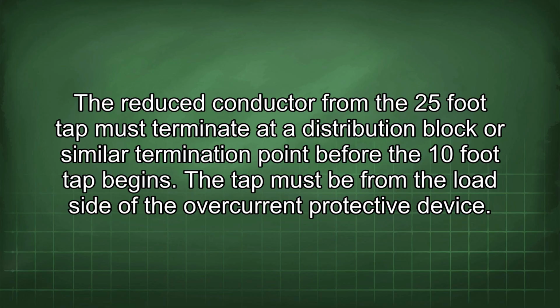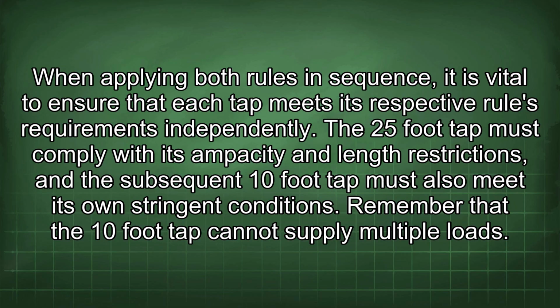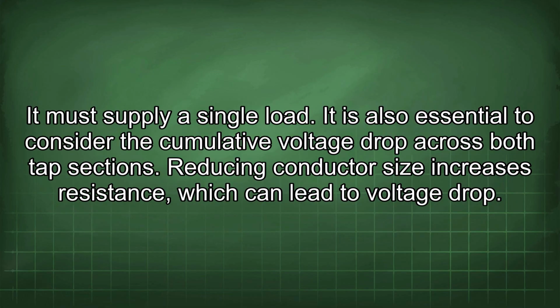The reduced conductor from the 25-foot tap must terminate at a distribution block or similar termination point before the 10-foot tap begins. The tap must be from the load side of the overcurrent protective device. When applying both rules in sequence, it is vital to ensure that each tap meets its respective rule's requirements independently. The 25-foot tap must comply with its ampacity and length restrictions, and the subsequent 10-foot tap must also meet its own stringent conditions. Remember that the 10-foot tap cannot supply multiple loads. It must supply a single load. It is also essential to consider the cumulative voltage drop across both tap sections. Reducing conductor size increases resistance, which can lead to voltage drop.